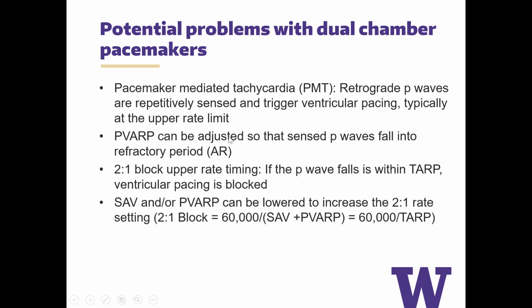You can adjust the refractory periods, this thing called the post-ventricular atrial refractory period, PVARP, and that can be adjusted so that the sensed P waves fall into this refractory period and are counted as atrial refractory sensed beats. And when it falls into the atrial refractory period, the pacemaker does not pace off of that. And so you can extend PVARP to treat PMT. Another thing that you can encounter in dual chamber pacemakers is a 2-to-1 or higher level pacemaker blocking pattern.